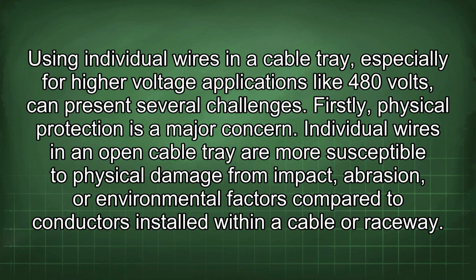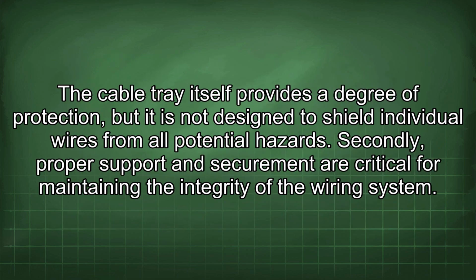Firstly, physical protection is a major concern. Individual wires in an open cable tray are more susceptible to physical damage from impact, abrasion, or environmental factors compared to conductors installed within a cable or raceway. The cable tray itself provides a degree of protection, but it is not designed to shield individual wires from all potential hazards. Secondly, proper support and securement are critical for maintaining the integrity of the wiring system.